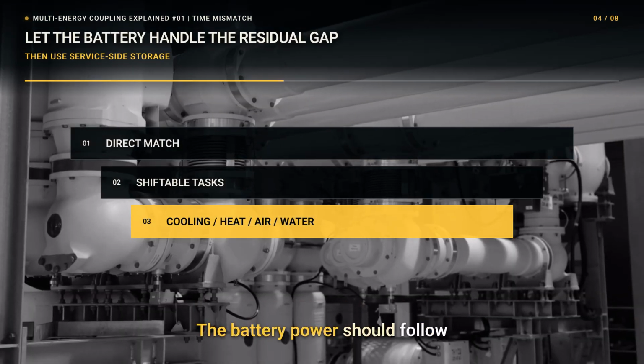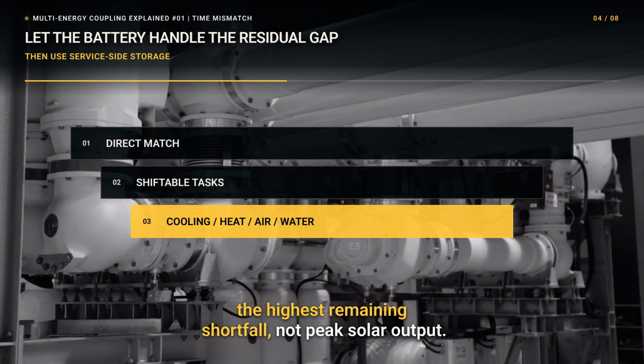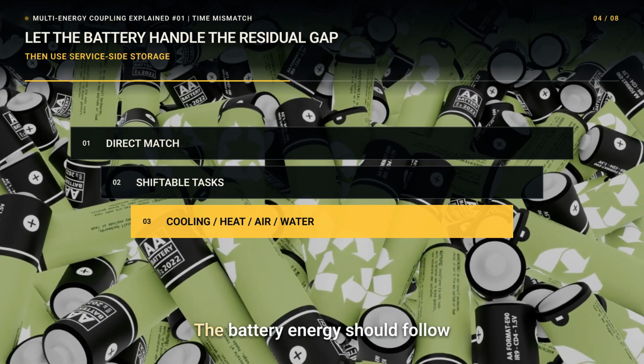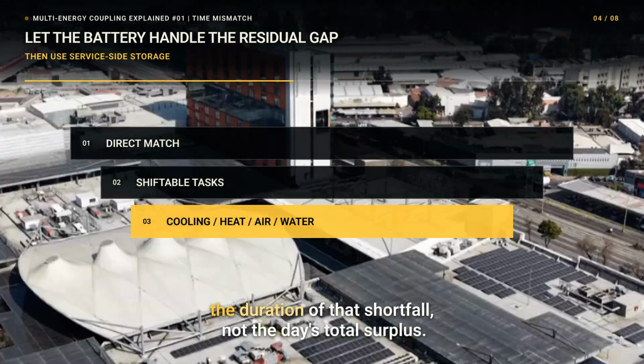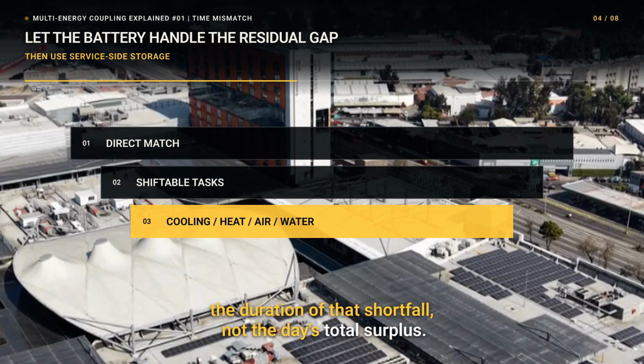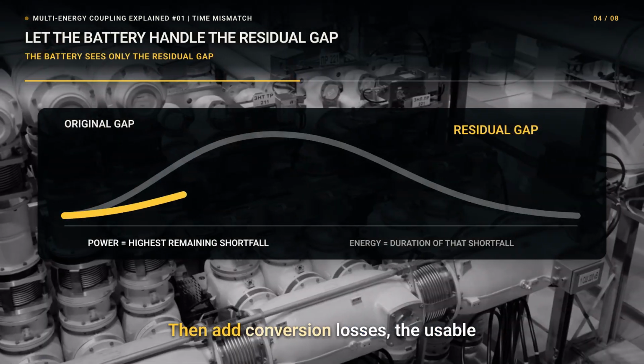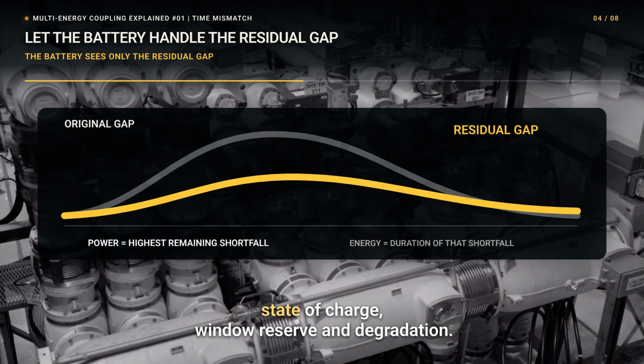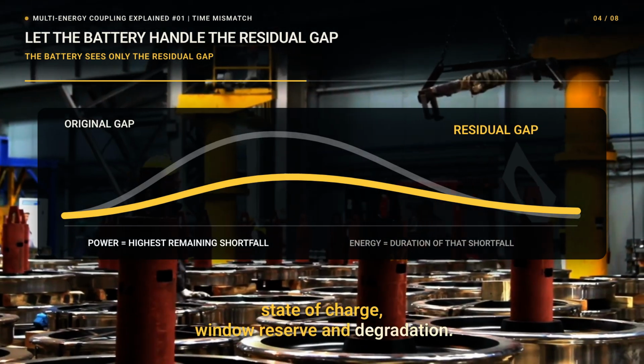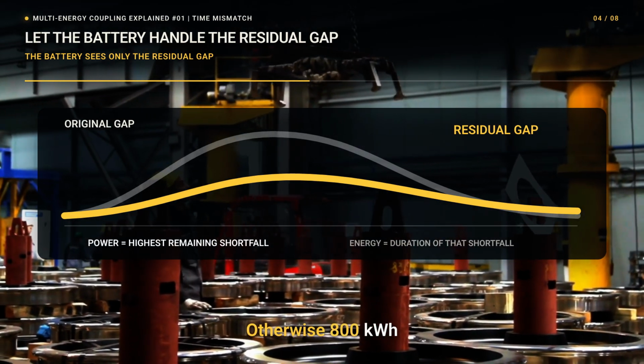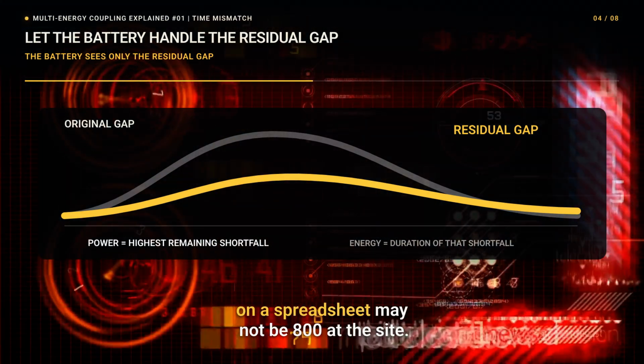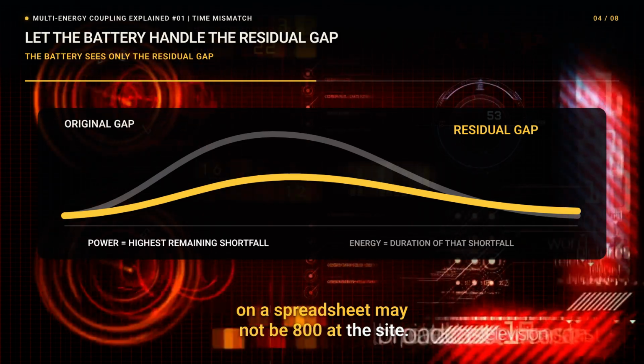The battery power should follow the highest remaining shortfall, not peak solar output. The battery energy should follow the duration of that shortfall, not the day's total surplus. Then add conversion losses, the usable state of charge window, reserve, and degradation. Otherwise, 800 kilowatt-hours on a spreadsheet may not be 800 at the site.